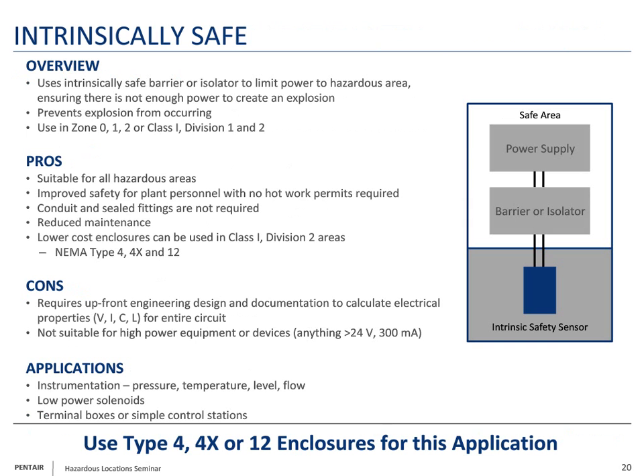Intrinsically safe is another alternative protection concept. What it does is it uses an intrinsically safe barrier or isolator to limit power that goes to a hazardous area, typically to an intrinsically safe sensor or instrument. It really prevents explosions from occurring because there's not enough power to create a dangerous situation. It's applicable in all hazardous areas, and it allows lower cost enclosures to be used in Class 1 Division 2 areas, like a NEMA Type 4, 4X, or 12. The challenge with it is it does require some upfront engineering design and documentation to make sure that the electrical properties of the circuit are accurate and work, and that it maintains intrinsically safe properties.